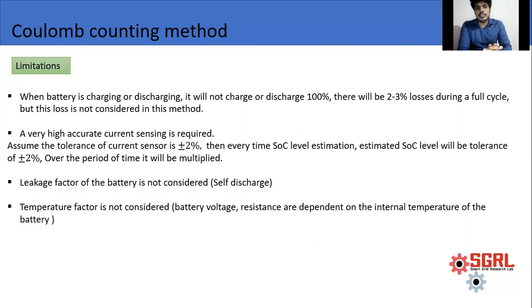The last limitation is that the temperature factor is not considered. When we charge or discharge the battery, the internal temperature will vary highly, but that variation is not considered in this method.